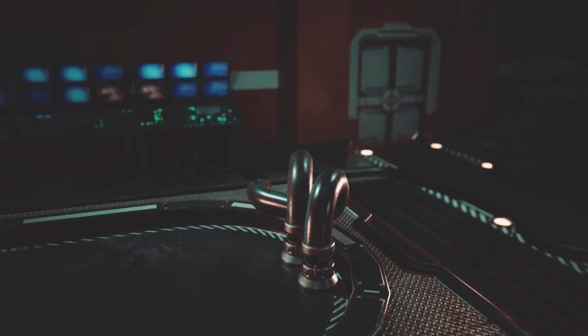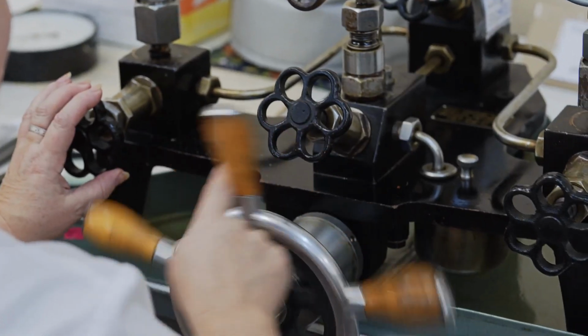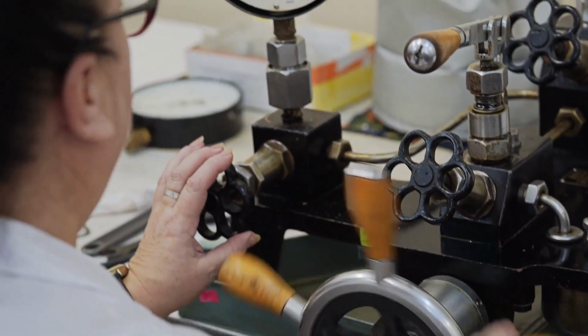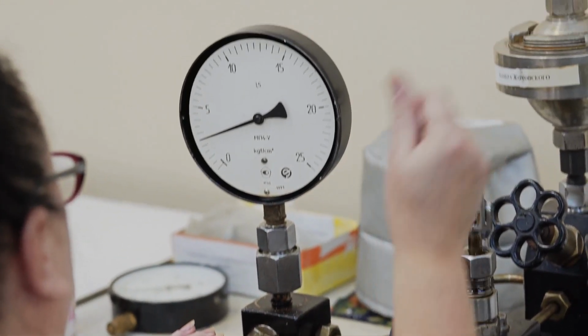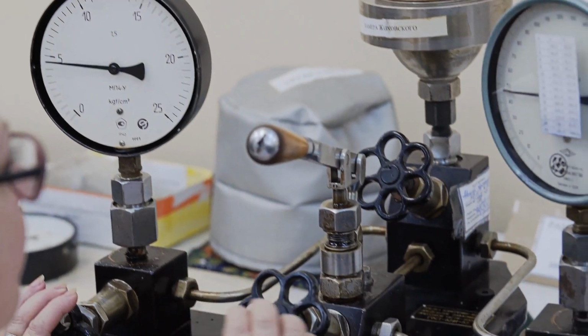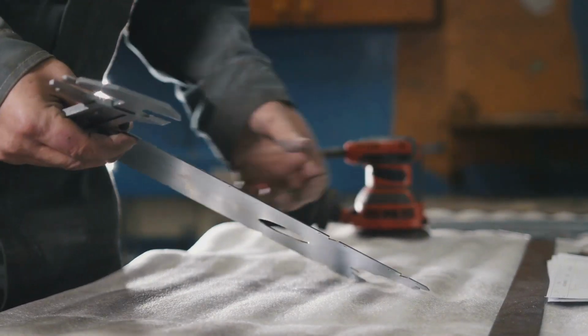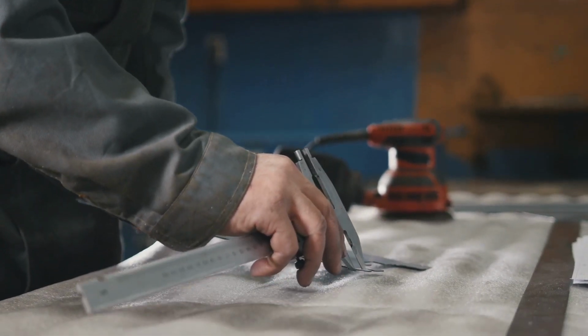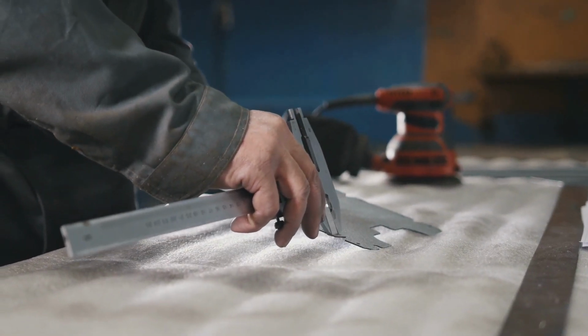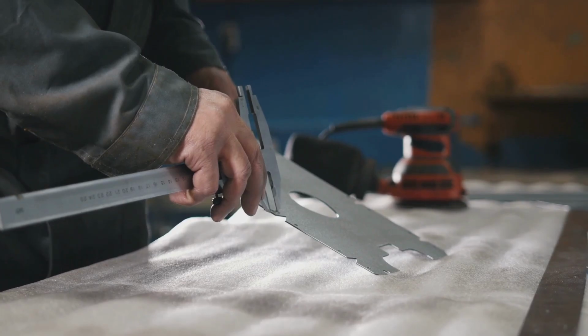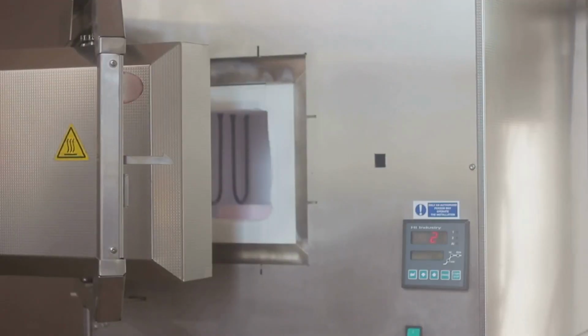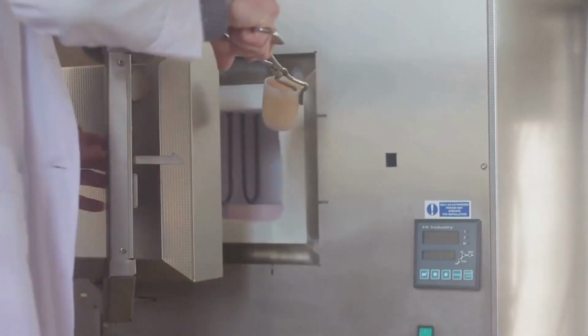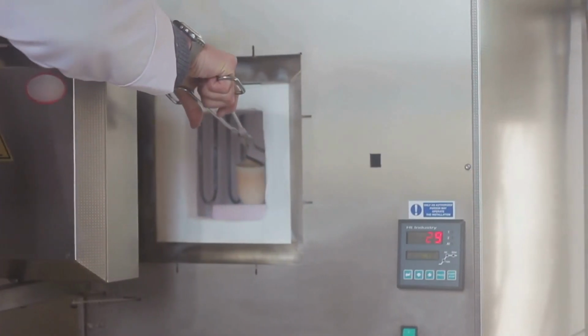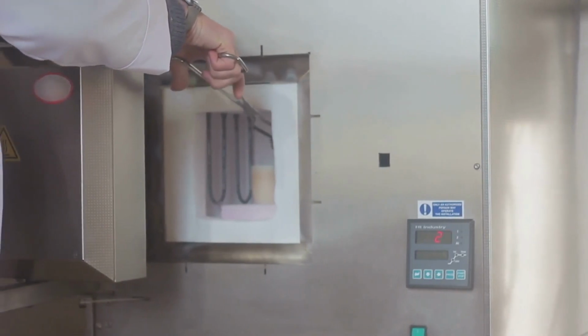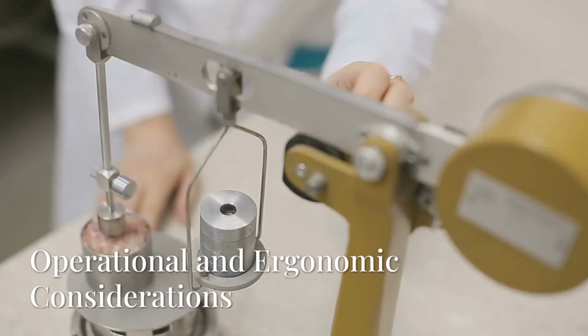Many different types of extensometers exist to suit a wide variety of applications. When selecting an extensometer, it's important to consider the specific material and testing requirements of each application. For example, some materials, such as thin films, are best tested with non-contact instruments to avoid damage from contact. Additionally, some samples may need to be inspected at elevated temperatures and require non-contact extensometers to maintain measurement accuracy.